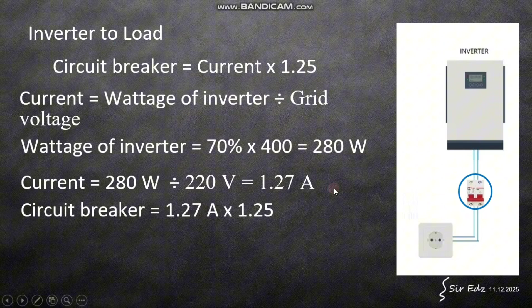We divide it by the grid voltage. Here in the Philippines, or mostly in Southeast Asia, it's around 220 volts, so we get 1.27 ampere. Multiplying by the safety factor of 1.25, we get 1.58, so around 2 ampere for the AC breaker.